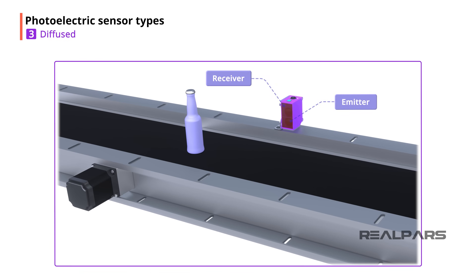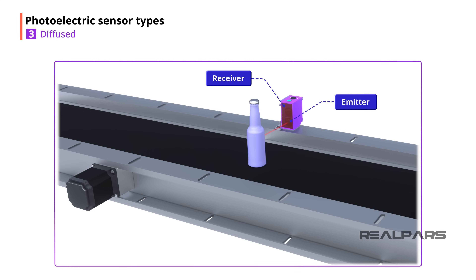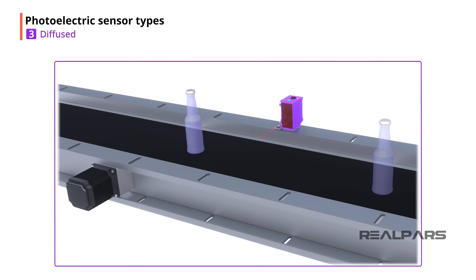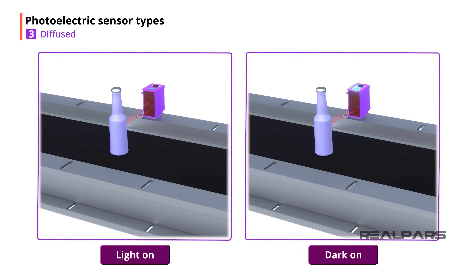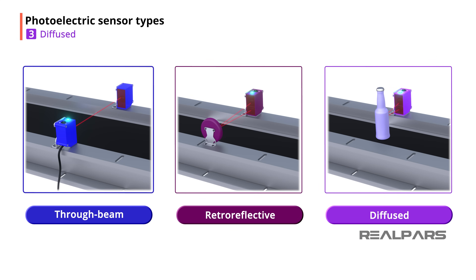Diffused photoelectric sensors have the emitter and receiver together in the same component. For the diffused sensor to work, the sensor's emitter needs to be pointed at an object so the light travels from the sensor's emitter to the object and then bounces back to the sensor's receiver. The diffused sensor output works the same as the through-beam and retro-reflective sensor outputs. Diffused sensors can also have a light on/dark on mode selector switch. The main disadvantage of using a diffused sensor is it has the shortest detection range of the three sensors, because depending on the object's shape, size, and color, it might not reflect light very well back to the sensor's receiver.